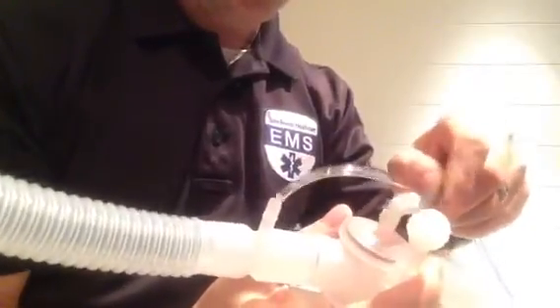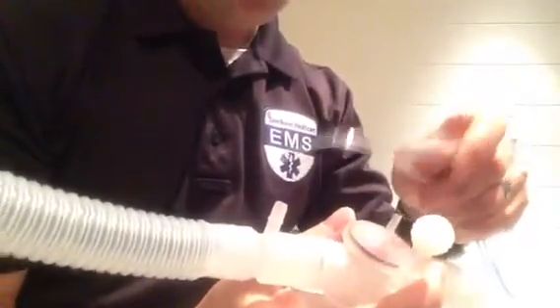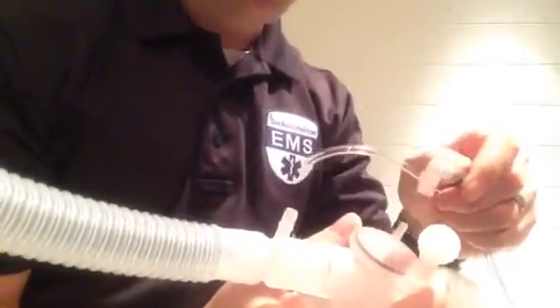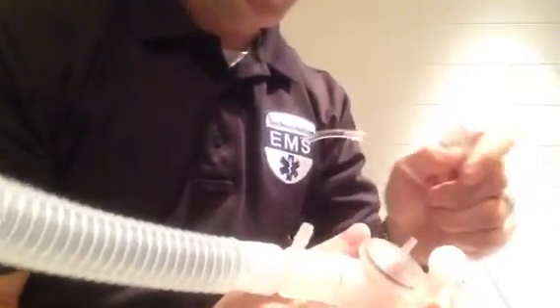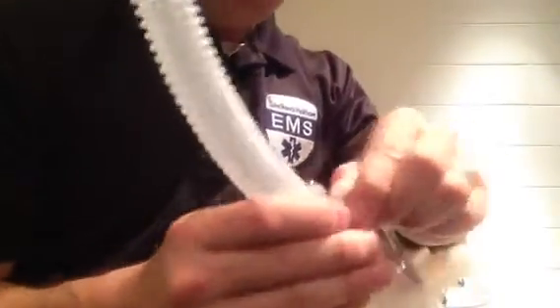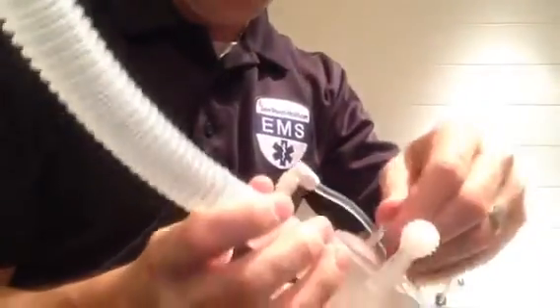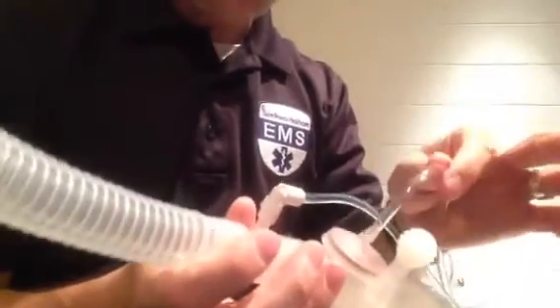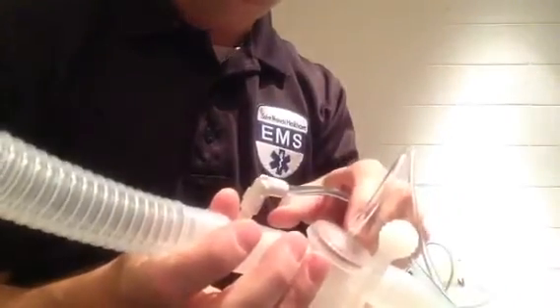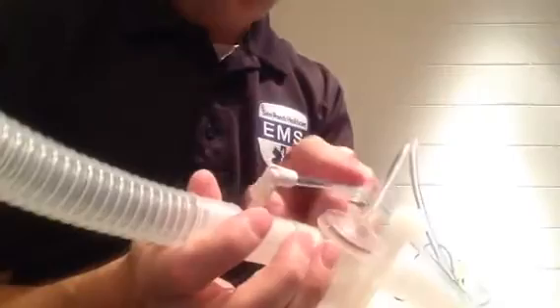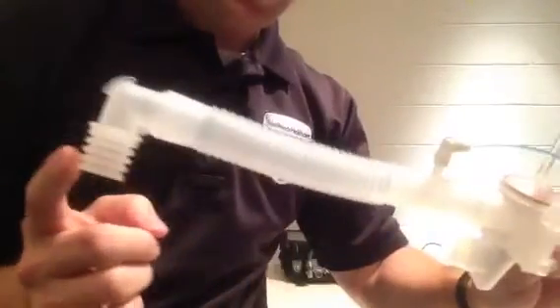If you try to put it on the narrow one, it won't stick. So the only way you could goof this up is to be really creative and use tape. So if you're using tape, you know you're doing it wrong. We put this where it belongs, and put this guy where it belongs, and now we know the white line is connected to the exhalation valve. The blue line, since this is connected to the patient, the blue line is proximal to the patient.